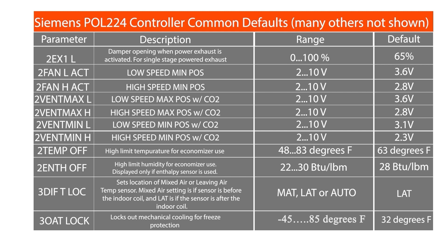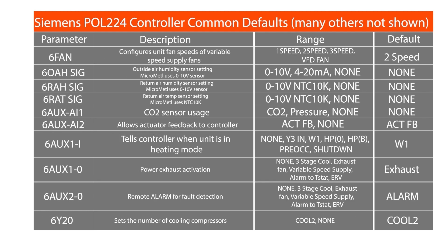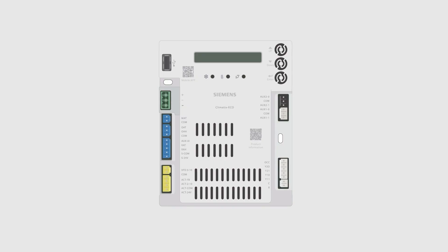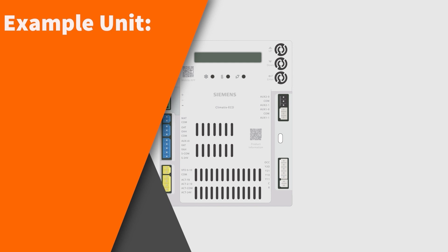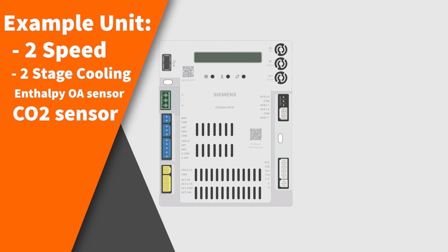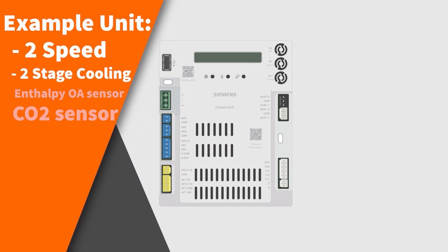The controller has defaults set for typical installations, though some units and some applications require changes from the default settings. This chart shows some of the more common controller defaults. For this example, we are going to set up a two-speed, two-stage cooling unit with an enthalpy outside air sensor and a CO2 sensor.